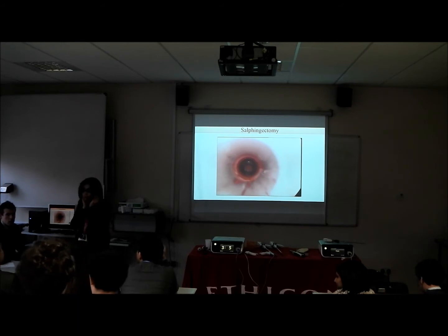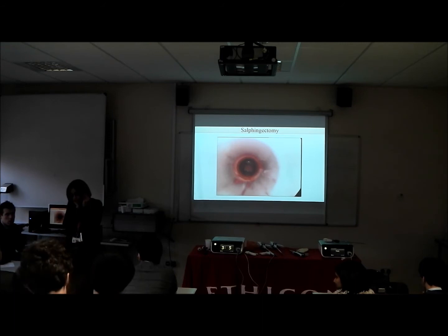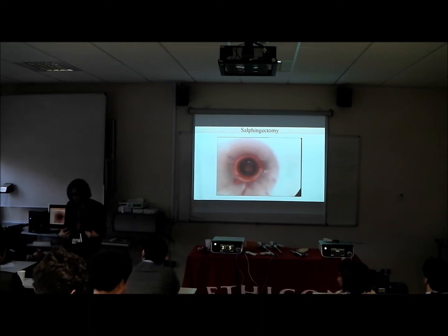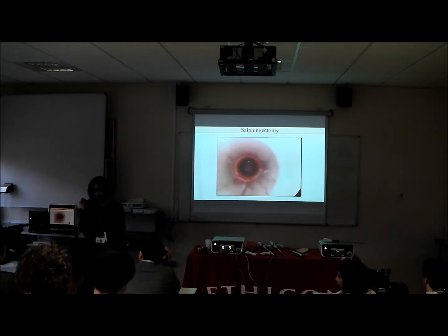No, because the majority of it will go out. The body will not store it. See? Yes, it's grounded because you're on the table and the table is grounded. So the majority of the patient is part of the circuit, but when the current comes out of the patient's body, it's all grounded and returned to the generator.